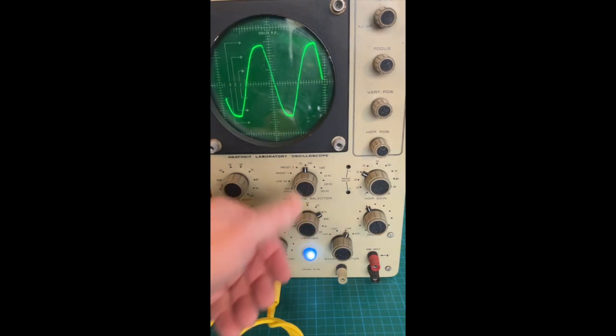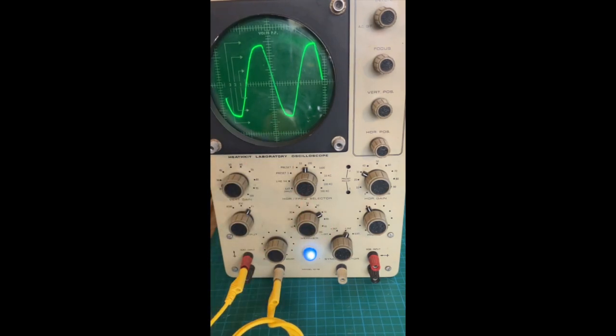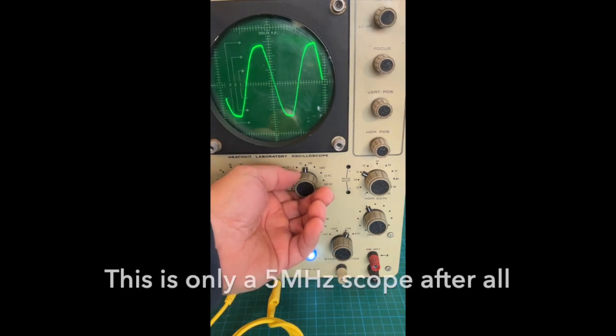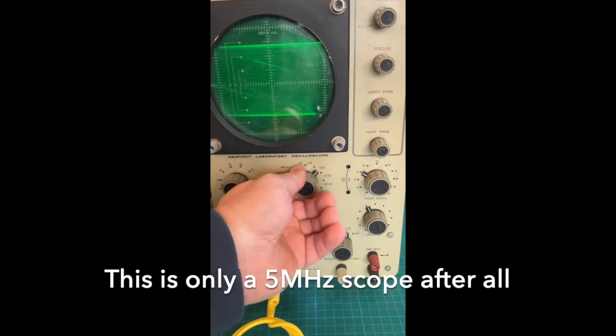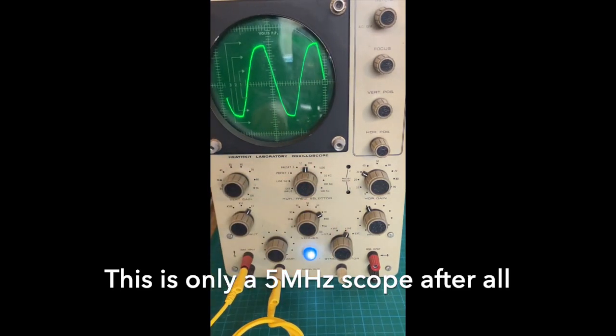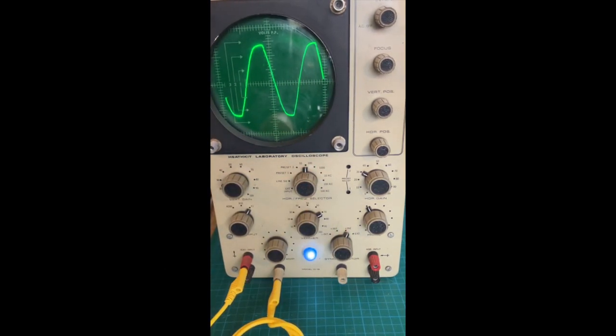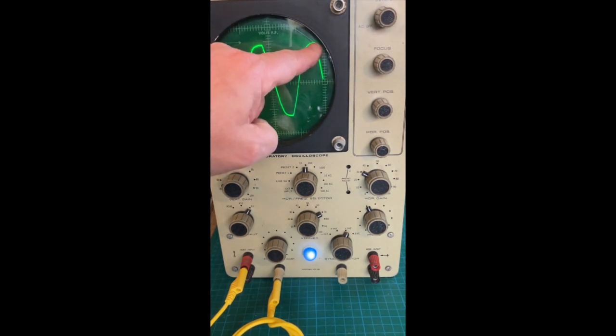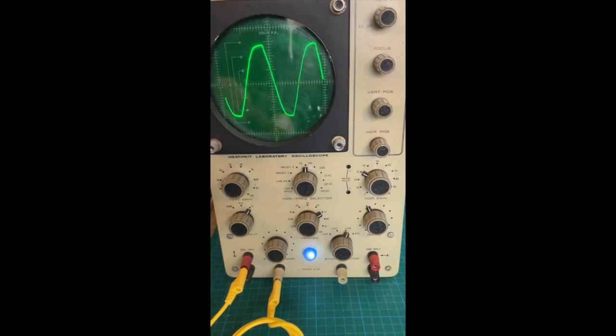So now we're sweeping at, I guess, 30 hertz, and the sweep range goes from a nominal 10 all the way to a nominal 500,000 hertz. You can even detect a little bit of nonlinearity between the size of these two cycles on the lowest one. So that cap will be replaced.